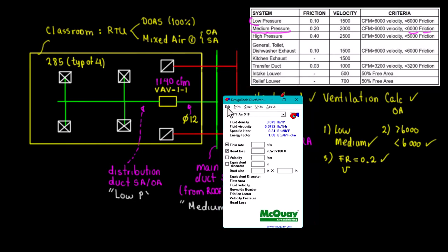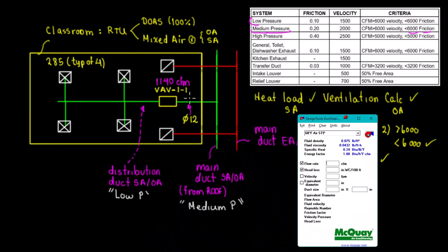So let's go here. Before, upstream is going to be 12 inches, that's the diameter. And what about this size? Now we're in business. I'm going to put a star in here, with orange, just to see where we are. So we're right here. We need to size that part of the ductwork after the VAV. What is the CFM at that start point? That CFM is 1140 CFM.